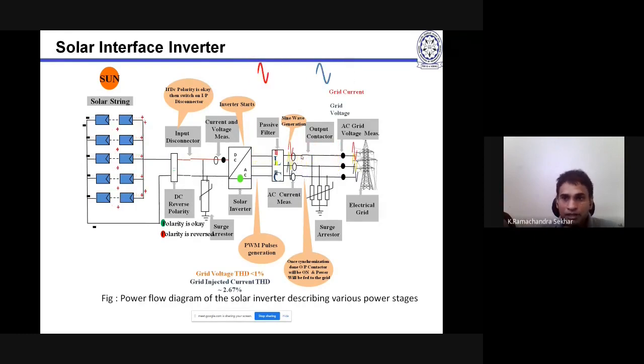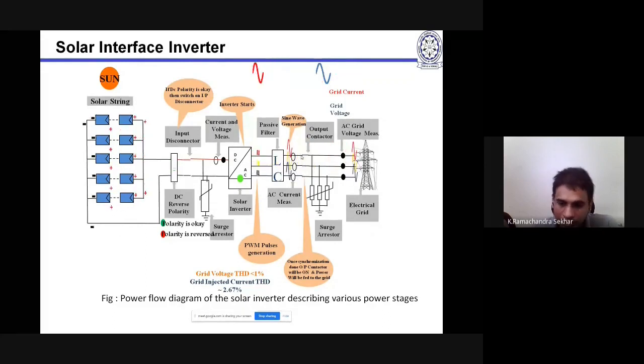Before going to the next step, we have to understand the THD requirement of the grid. The solar panel should operate below 3% THD. The total harmonic distortion should be below 3%. That is the Indian grid standard. For that we increase the switching frequency, and different people have adopted different filters, but the basic aim is to achieve THD less than 3%. Voltage THD is based on the grid voltage because we are sensing the grid voltage. At 1% of grid voltage THD, 3% current THD is required. Otherwise, you cannot integrate with the grid.